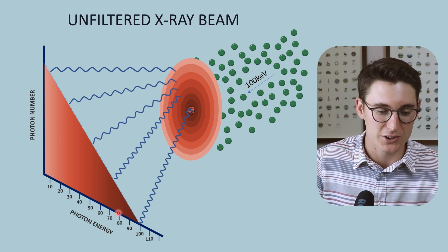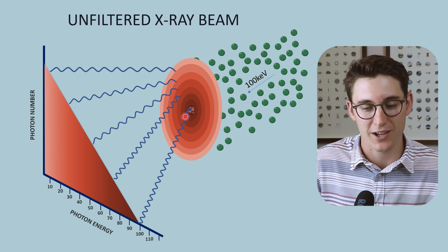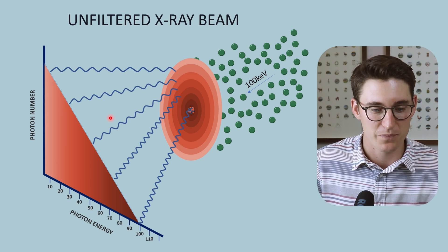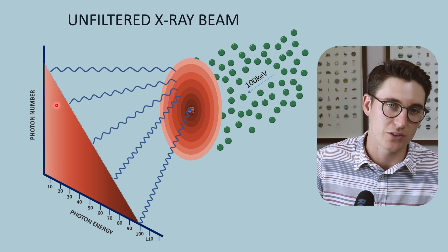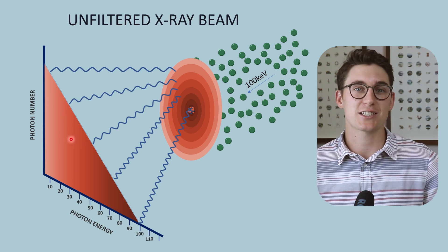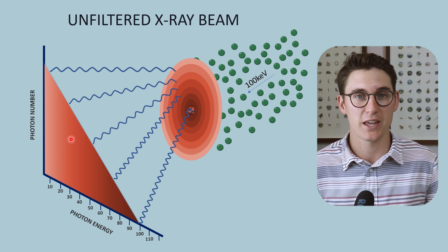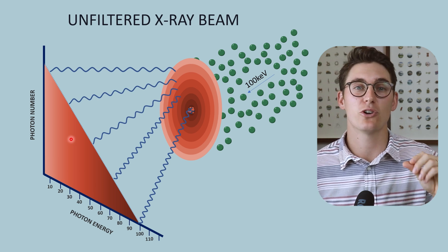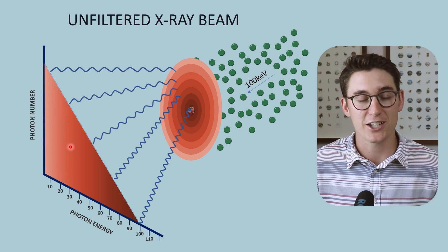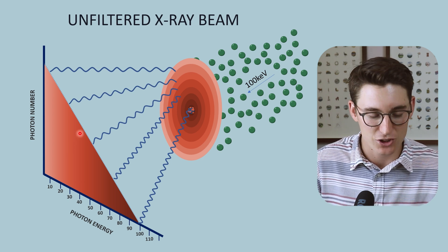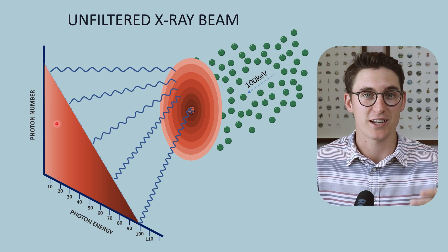This is our unfiltered Bremsstrahlung radiation curve — all the x-rays produced at the anode through Bremsstrahlung radiation. The vast majority are low energy photons. These photons interact with matter within our patient, releasing photoelectrons and inferring dose to our patient. These low energy x-rays are much more likely to be attenuated and not reach the x-ray detector, so they contribute to patient dose but not to our image.